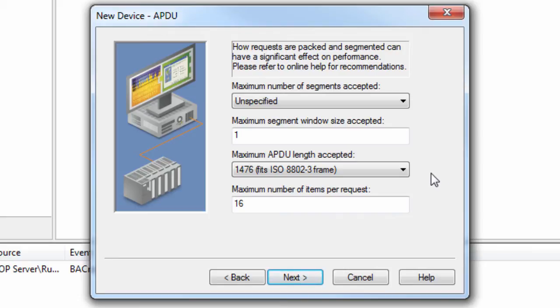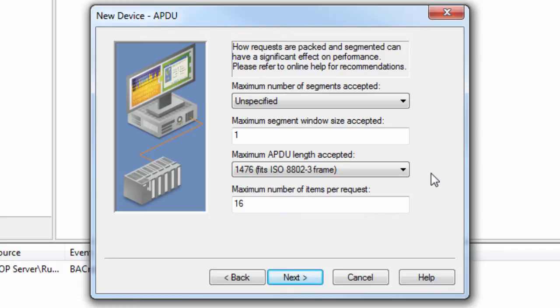In most cases, the default settings are acceptable. The maximum number of items per request limits the number of items that can be packed into read property multiple and write property multiple service requests. The actual number of items packed into a request can vary depending on how many items are due for reads or writes at a given time. Generally, the higher the value, the better the performance. For large requests or responses, however, performance gain may be diminished by message segmentation.